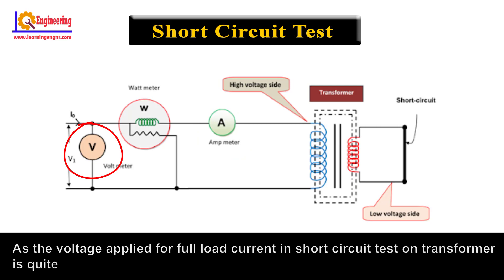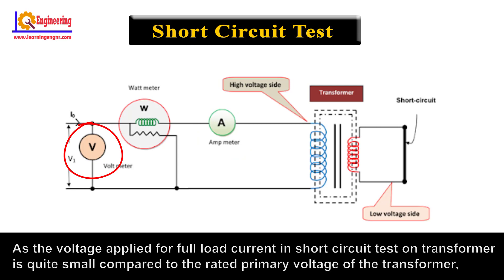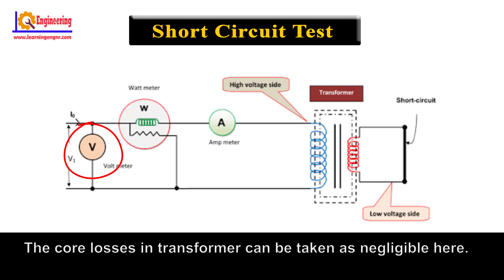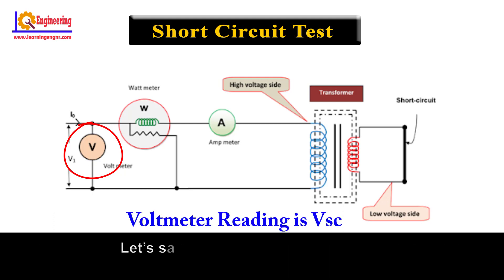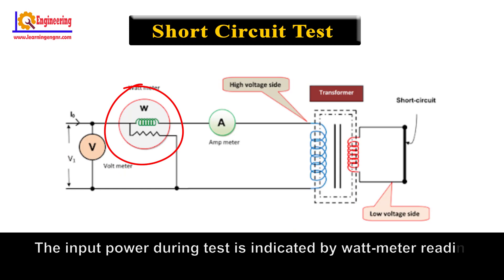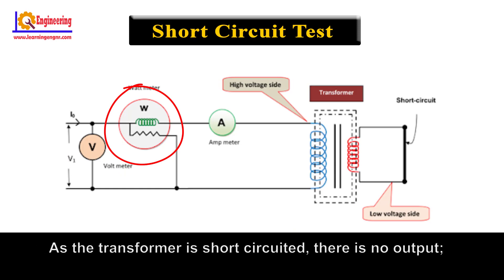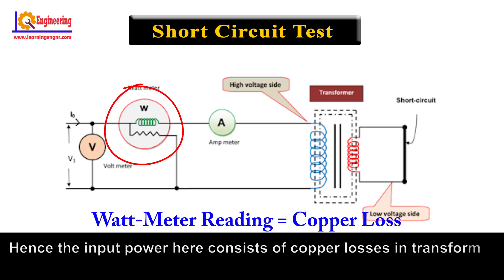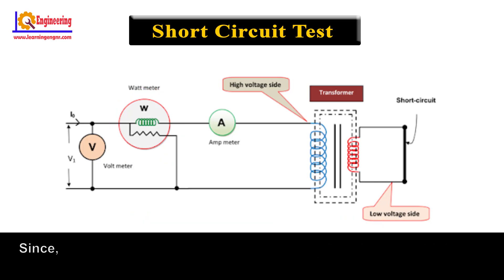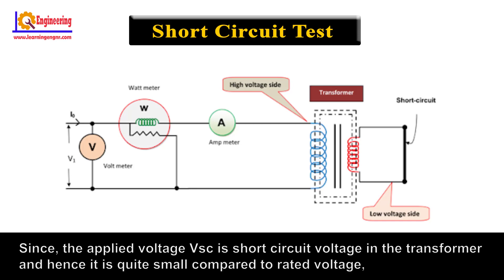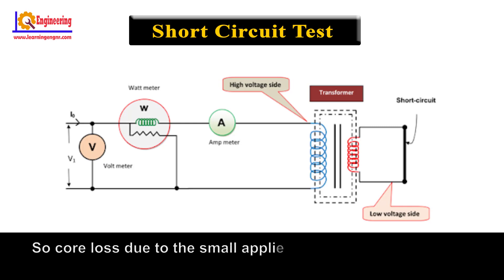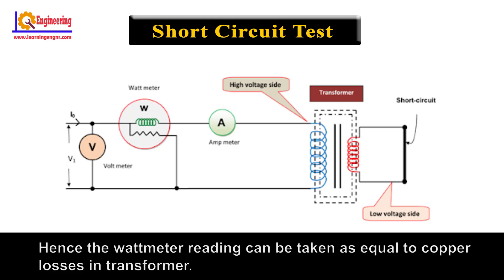As the voltage applied for full load current in the short circuit test on transformer is quite small compared to the rated primary voltage of the transformer, the core losses in the transformer can be taken as negligible. The voltmeter reading is VSC. As the transformer is short circuited, there is no output, hence the input power consists of copper losses in the transformer. Since the applied voltage VSC is quite small compared to rated voltage, core loss due to the small applied voltage can be neglected. Hence the wattmeter reading can be taken as equal to copper losses in the transformer.